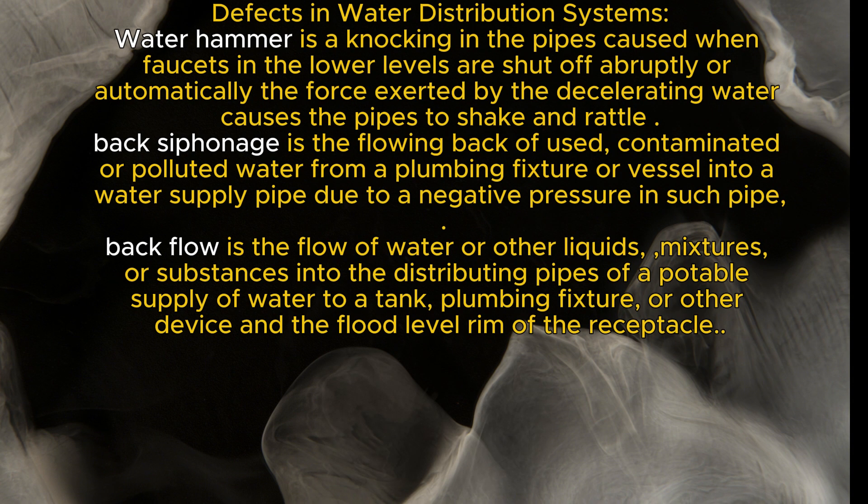Defects in water distribution systems. Water hammer is a knocking in the pipes caused when faucets in the lower levels are shut off abruptly or automatically; the force exerted by the decelerating water causes the pipes to shake and rattle. Back-siphonage is the flowing back of used, contaminated, or polluted water from a plumbing fixture or vessel into a water supply pipe due to a negative pressure in such pipe.